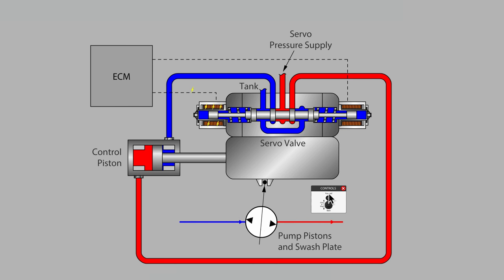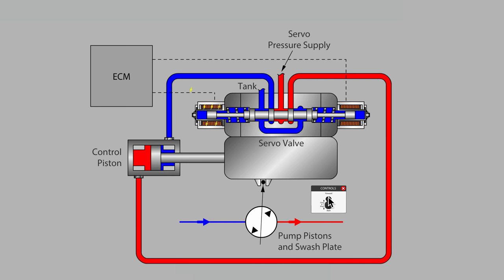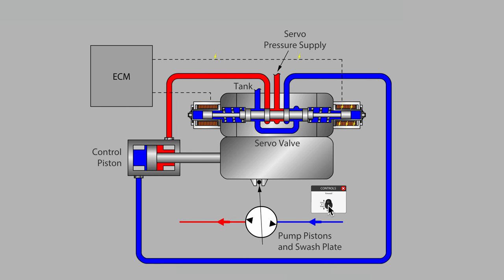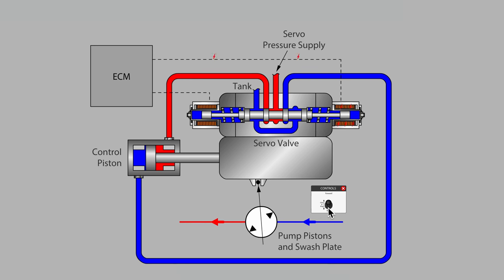Increased swashplate angle results in a longer piston stroke and higher flow rate from the pump's right-hand port. Decreasing the current allows pressure in the control piston to be vented gradually to tank. Moving the control lever past the center point causes flow to be displaced from the pump's left-hand port.